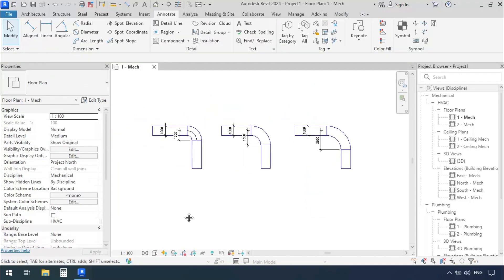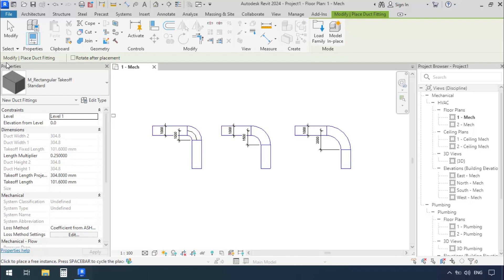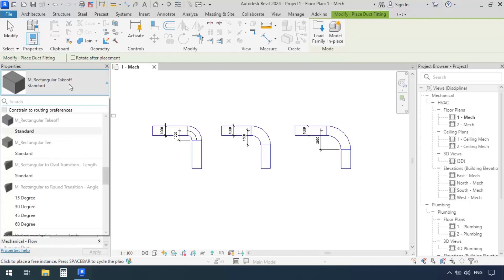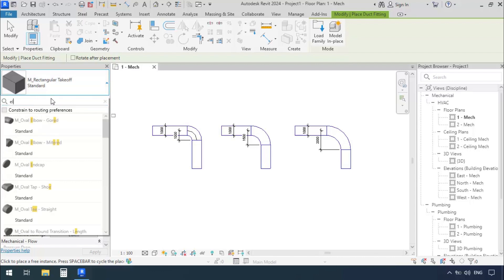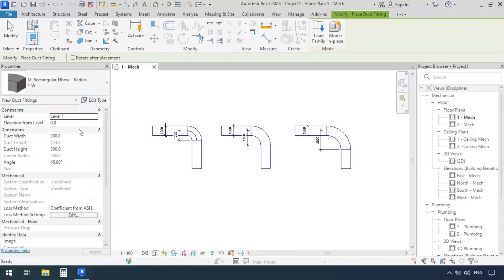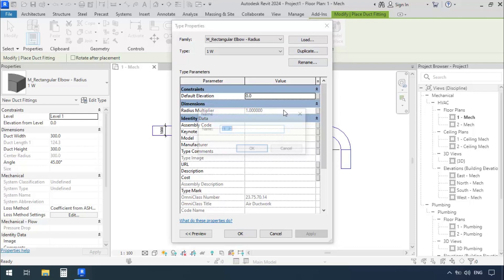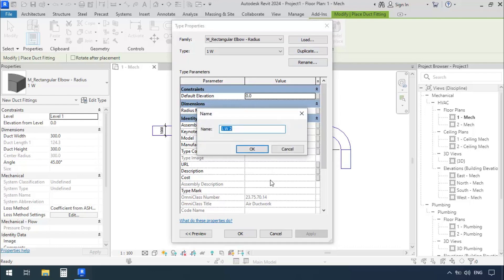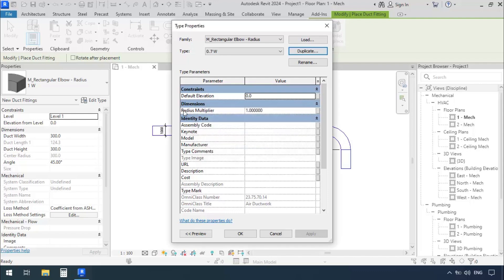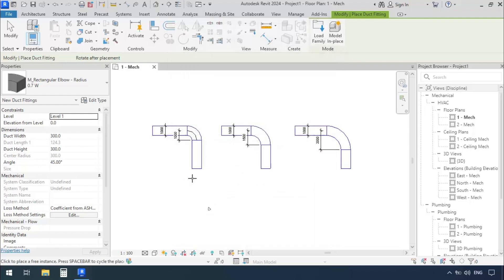The question is, can we add a new radius of our own? Sure, we can. We'll go to the Systems tab, find and click on Duct Fitting. In the Properties window, we'll find Rectangular Elbow. We can go to this box which says Search and type in Elbow. We see the ones that say Rectangular Elbow Radius. We'll select one, then go to Edit Type. Before we change anything, we have to click Duplicate. For example, I'll type in 0.7W. I'd like the radius of my elbow to be 0.7 times the width of the duct. We see it says Radius Multiplier. We'll type in 0.7 and click OK.